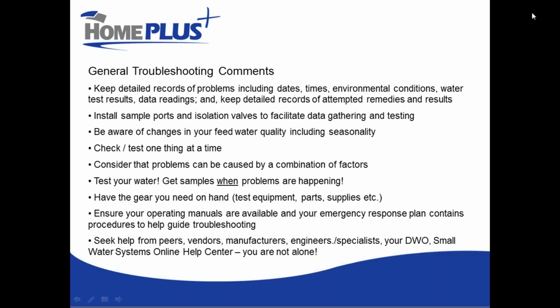On the be prepared side of things, having sample ports and isolation valves throughout your system is very handy for enabling us in troubleshooting to grab samples before and after each piece of equipment. It can help us determine where the root of a problem is occurring. Isolation valves might allow you to shut off water to a particular aspect of the plant. And I'm going to use the word bypass carefully here. When I say bypass, this can be useful sometimes to temporarily bypass, say, a turbidity filter to determine whether or not we have a pressure loss there.